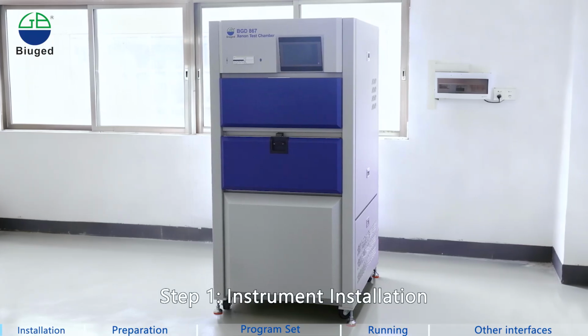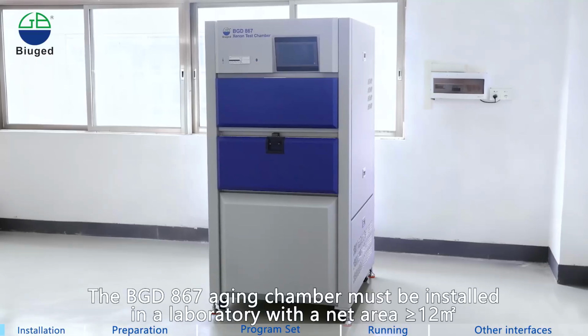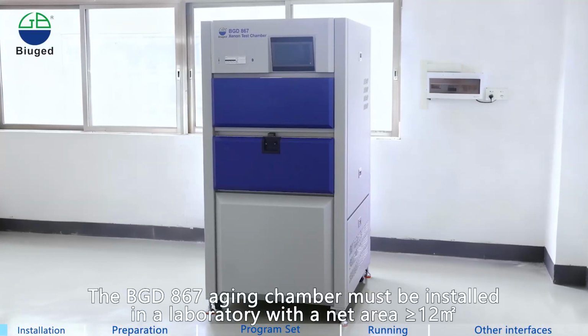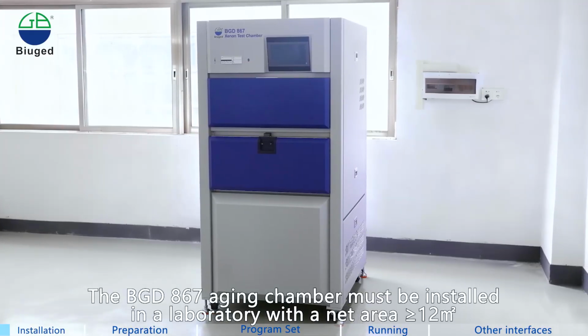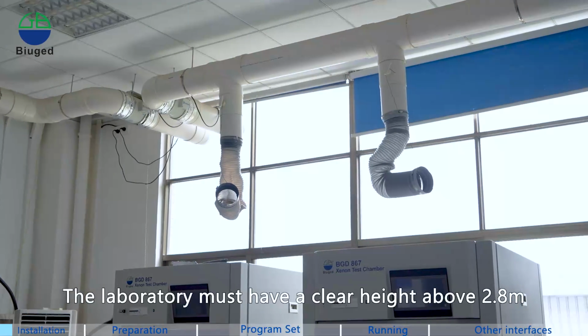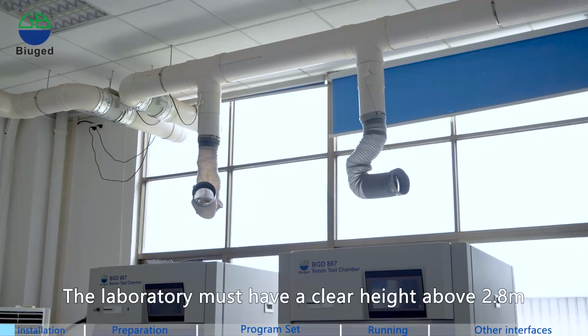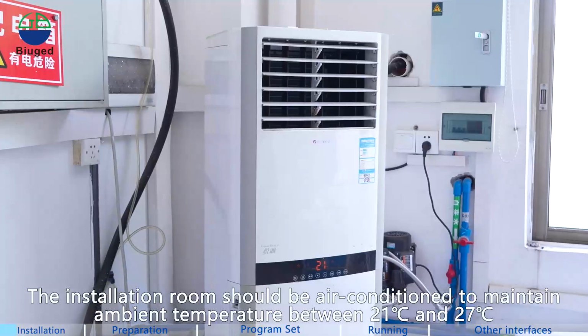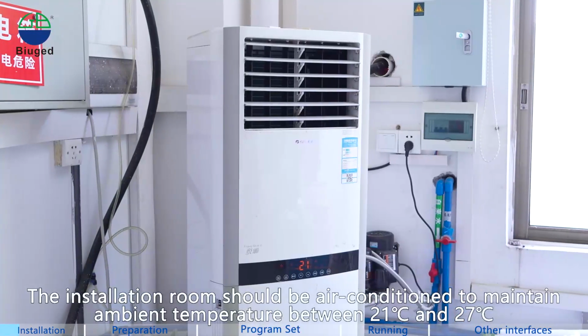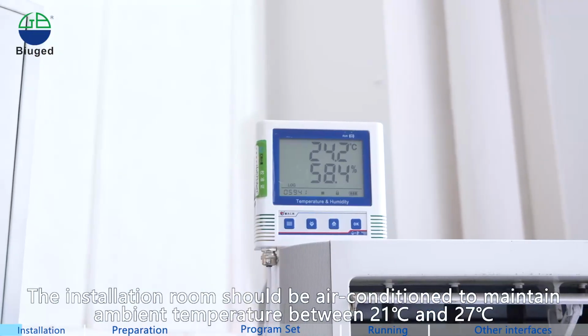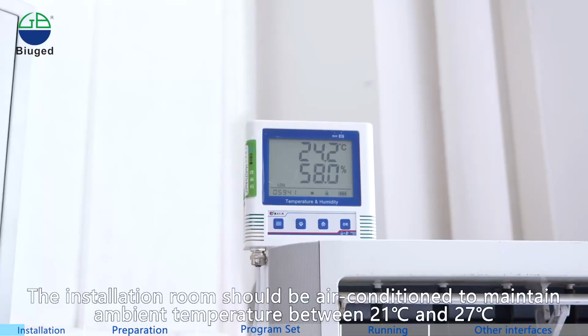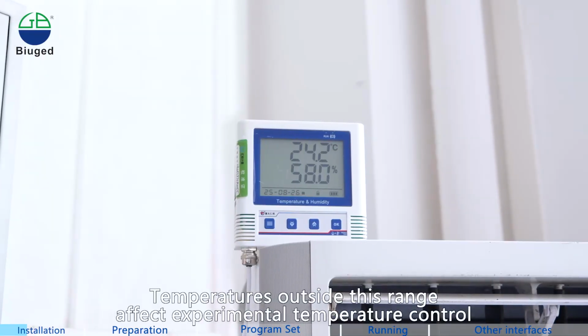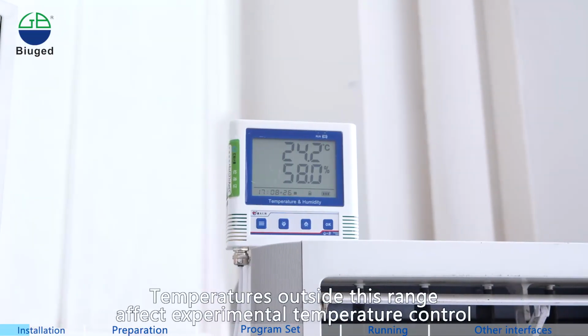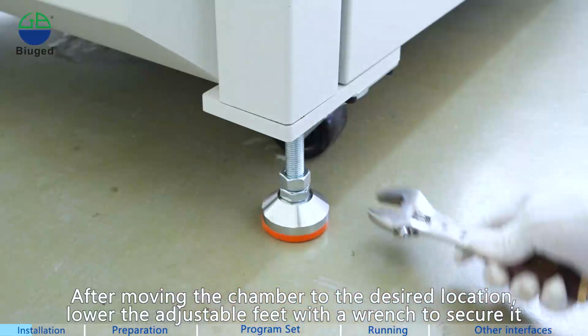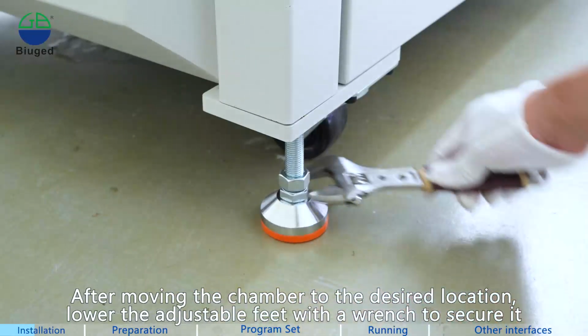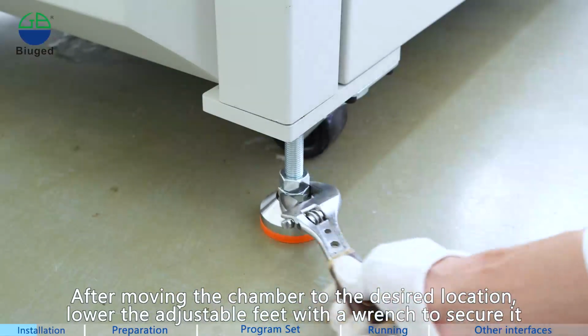Step 1. Instrument installation. The BGD 867 aging chamber must be installed in a laboratory with a net area greater than or equal to 12 square meters. The laboratory must have a clear height above 2.8 m. The installation room should be air-conditioned to maintain ambient temperature between 21 degrees Celsius and 27 degrees Celsius. Temperatures outside this range affect experimental temperature control. After moving the chamber to the desired location, lower the adjustable feet with a wrench to secure it.